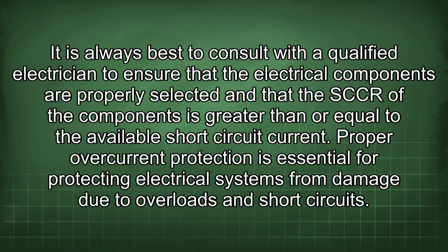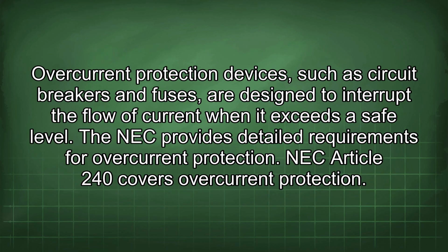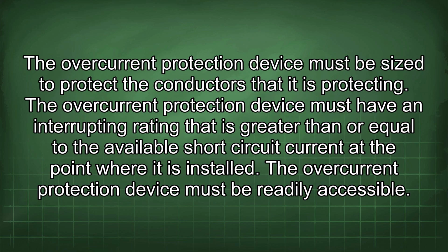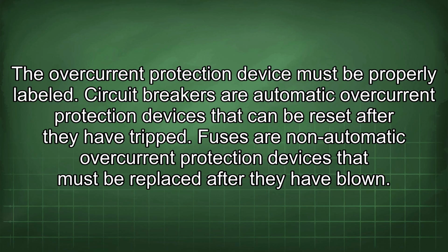Proper overcurrent protection is essential for protecting electrical systems from damage due to overloads and short circuits. Overcurrent protection devices, such as circuit breakers and fuses, are designed to interrupt the flow of current when it exceeds a safe level. The NEC provides detailed requirements for overcurrent protection. NEC Article 240 covers overcurrent protection. The overcurrent protection device must be sized to protect the conductors that it is protecting. The overcurrent protection device must have an interrupting rating that is greater than or equal to the available short circuit current at the point where it is installed. The overcurrent protection device must be readily accessible. The overcurrent protection device must be properly labeled.